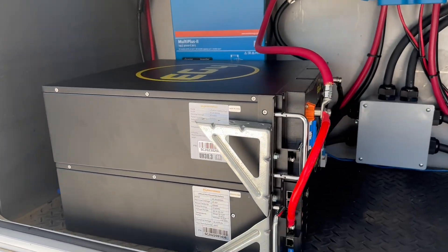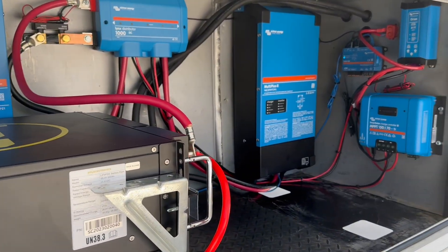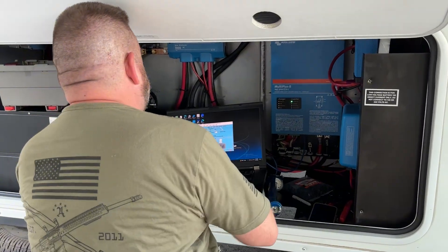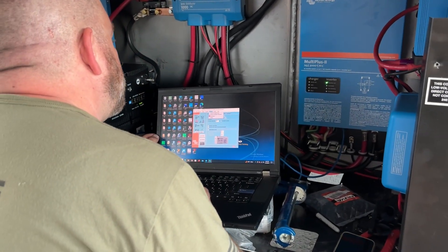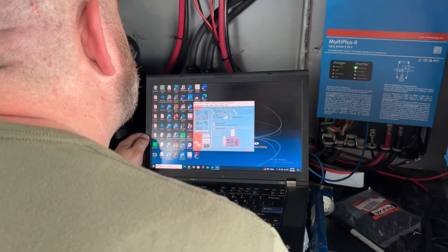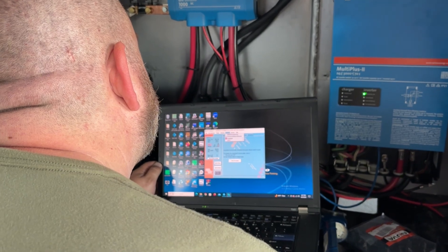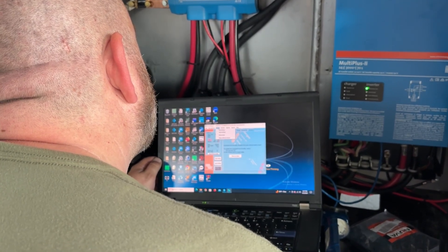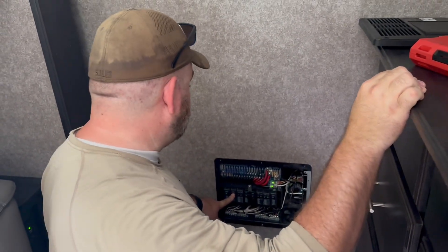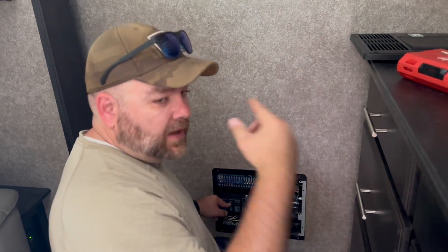You can see the positives connected going up to the Lynx distributor and the negatives going into the smart shunt. He's doing configuration for the MultiPlus 2s, getting them set up so communication between all products is smooth and accurate. When installing Victron MultiPluses or any AC inverter, you always want to turn the breaker off for your converter so it's not back-feeding into the batteries.